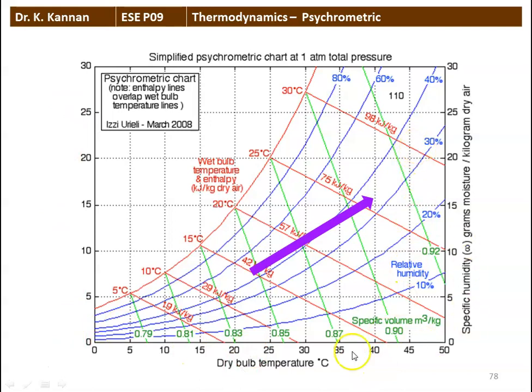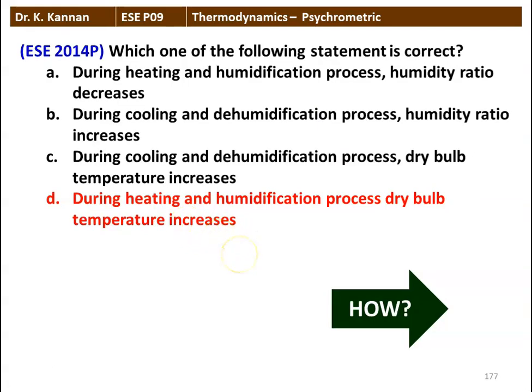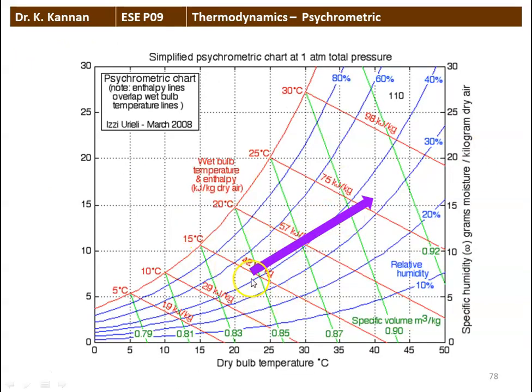This is the psychrometric chart. The x-axis is the dry bulb temperature and the y-axis is the specific humidity or humidity ratio. The blue color lines represent relative humidity, the red color inclined lines are the enthalpy lines, and the green color lines are the specific volume. The wet bulb temperature is measured on the saturated vapor line, along with enthalpy and dew point temperature. The process shown is heating and humidification, during which dry bulb temperature increases from approximately 22 degrees to 40 degrees and specific humidity increases.